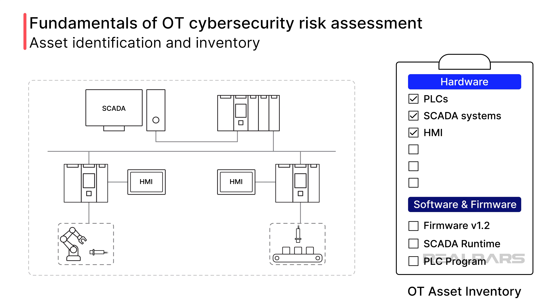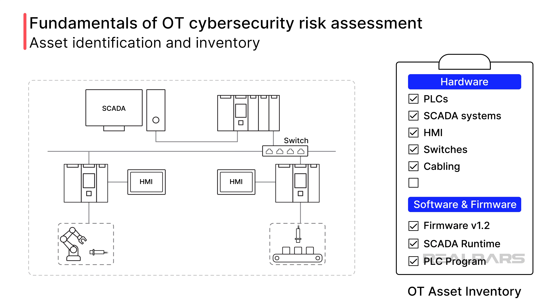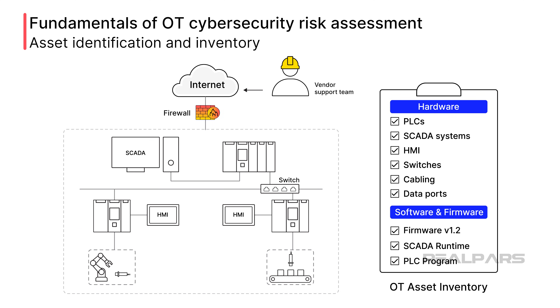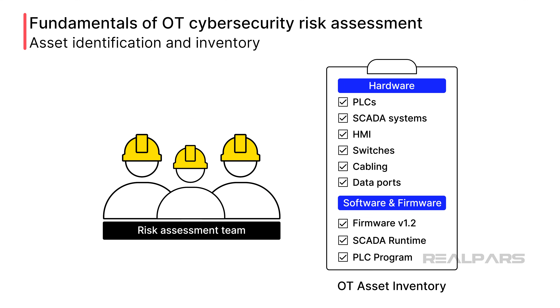This inventory must include all software and firmware installed on your OT systems. These assets may not appear to be physical in nature, but they are at risk and the easiest assets for hackers to infect. We must also include network equipment such as switches and cabling, and don't forget external connections such as data ports provided for vendor access or connections for remote maintenance. A complete inventory is crucial to allow the risk assessment team to fully understand the threat landscape, as missed items can be easy routes for system infection, even if not maliciously done.